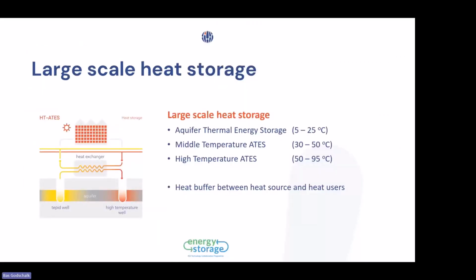But can we also go up with the temperatures? Because Romain also mentioned that in district heating systems, you need much higher temperatures. Now, the example we have is the Middenmeer project, where we went up to 80, 85, 90 degrees, which is the high temperature ATES system. The definition we use is chosen by us. I will explain why in the next slides, but it's not an official scheme. We often use it so that for traditional ATES systems we have storage temperatures between 5 and 25 degrees, middle range temperature between 30 and 50, 55, 60, and high temperatures up to 90 to nearly 95 degrees.